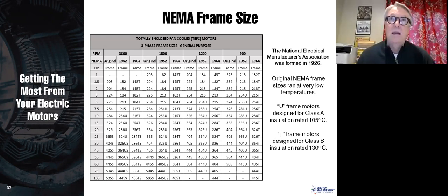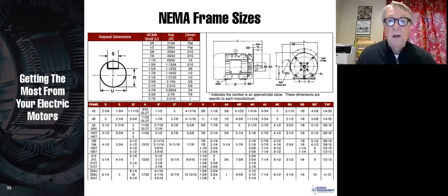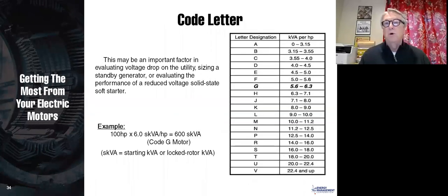That is 95% true. There are cases in which, even though the frame sizes are standardized, some parts of those motors may interfere and they may not work exactly as you expect. Here's your NEMA frame sizes, and notice all the dimensions. The shaft height, for instance, is part of your NEMA frame size, the length of the motor, the width of the shaft, and all of these dimensions are standardized based on a particular frame size. So in general, you want to specify the frame size when buying a new motor, and that should fit right in with where the old motor went.